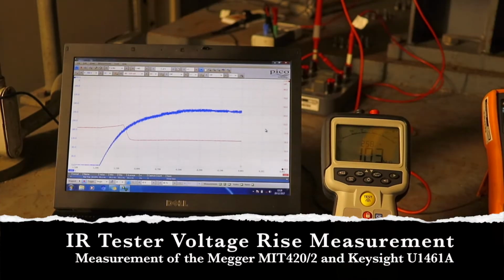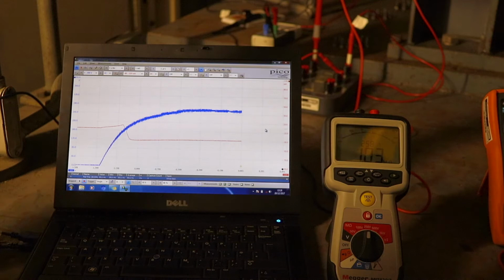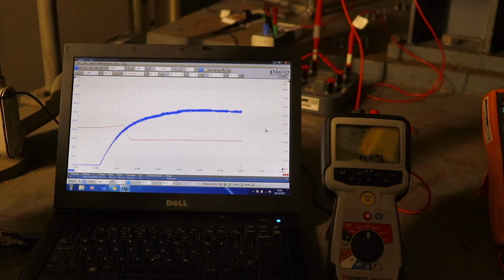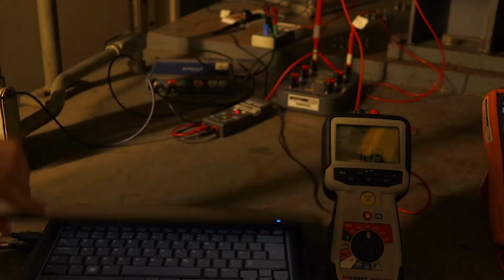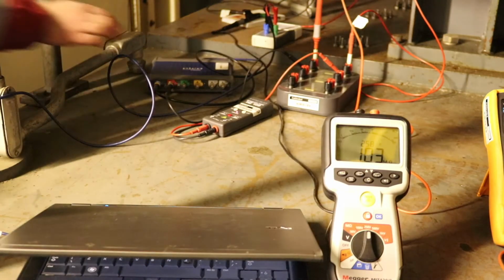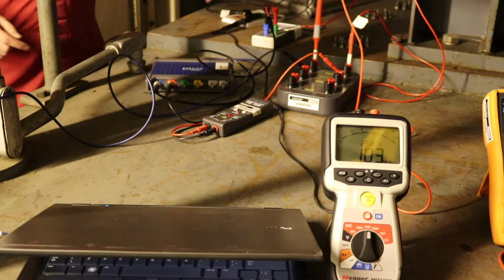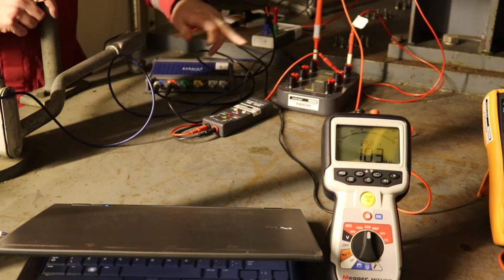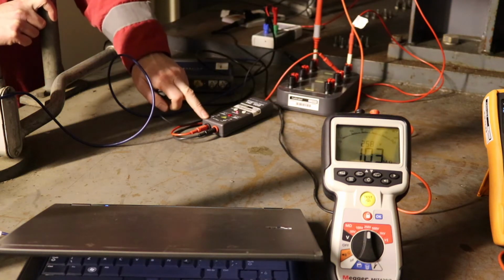So what I've done here, just to record some extra data, is set up an oscilloscope onto the output of the insulation tester. That's the picoscope there. It's actually running through an HV probe onto the winding that feeds back into the scope, back into the laptop. I'm also collecting the current via a 10 ohm shunt that is being picked up through a differential probe.